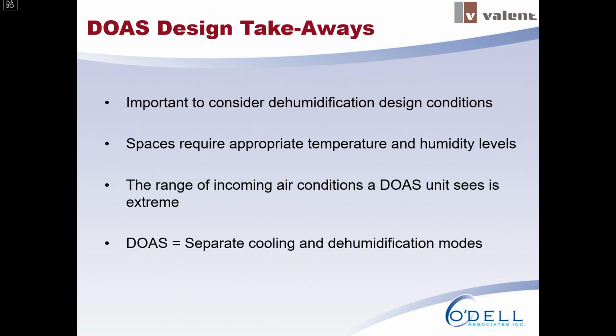So again, we're dealing with 100% outside air, so the range of temperatures and humidities entering the unit can fluctuate wildly, so modulation is critical. We'll talk about modulation in the subsequent slides. And then when you think of DOAS, be thinking about the different modes of operation, specifically the difference between cooling mode and dehumidification. So a DOAS unit's designed to handle all of those modes, and it's critical to think of those when laying out the unit. So now that we've covered these key DOAS design takeaways, Nathan's going to talk more about Valent's product offering.